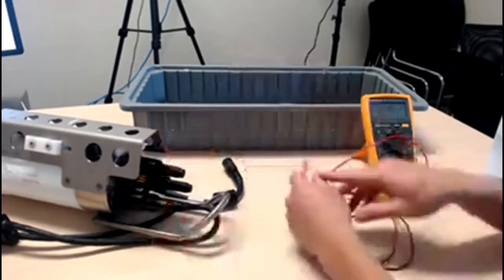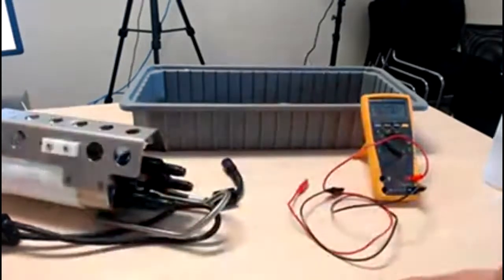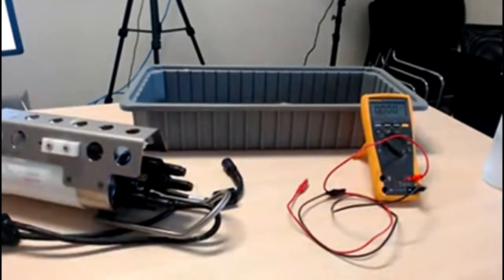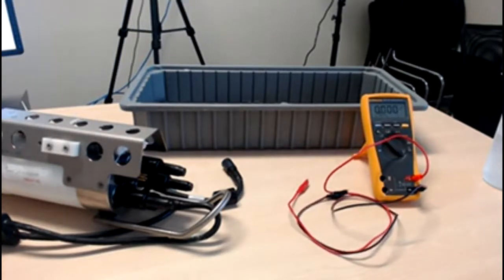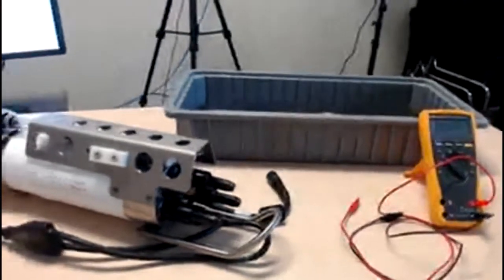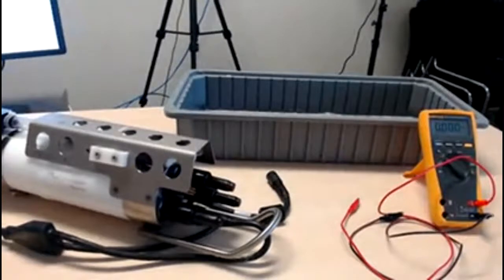Next thing I can do is simulate the data from the sensor using a AA battery. Because these sensors output a standard voltage, supposed to be a 0 to 5 volt signal, I can measure the voltage from the CTD with this command, TV. That's telling me the voltage from all of the sensors currently connected to the instrument.